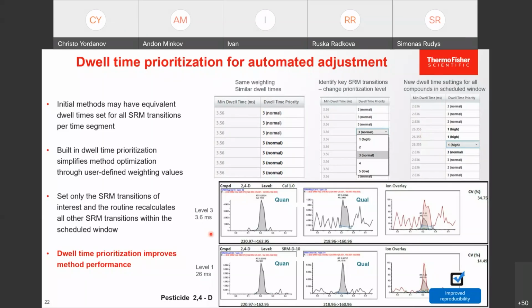If you take an example, if all the transitions were at level 3, which is normal, CVs were not good, then we improved for this compound, this pesticide. We put this compound on level 1 for high priority. We increased the dwell time, which gave improved reproducibility. So on one hand, you have a much better method optimization tool. You can set priorities on specific compounds, and other compounds would be automatically adjusted based on your settings.